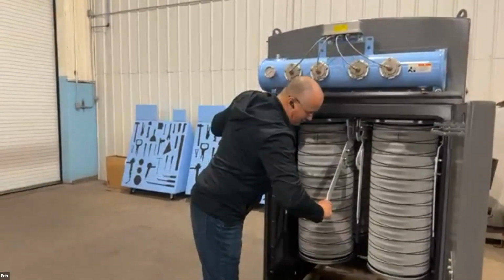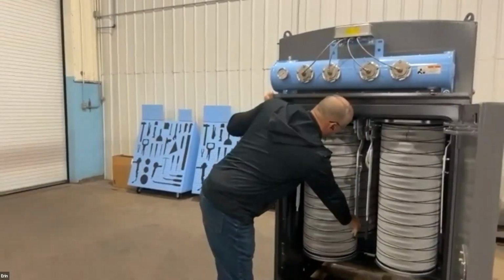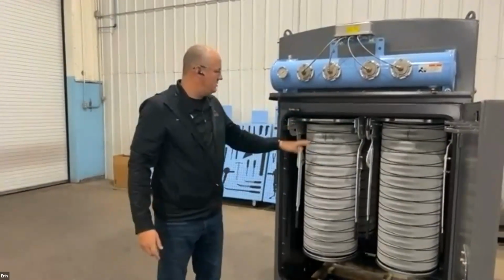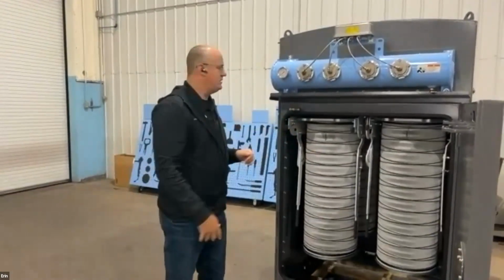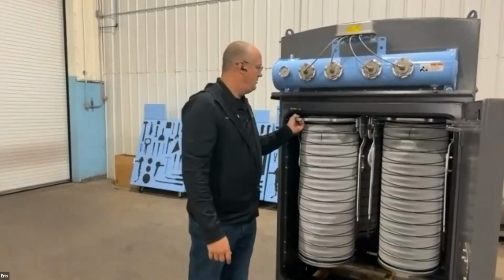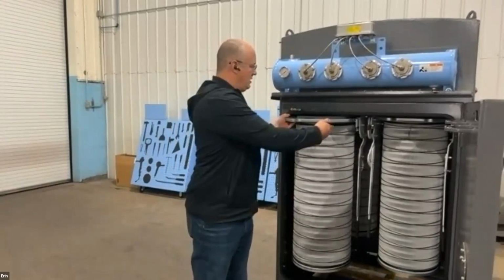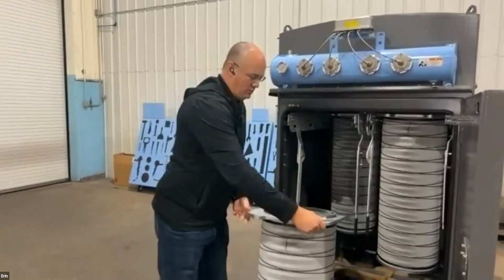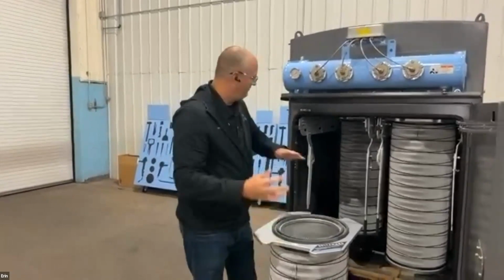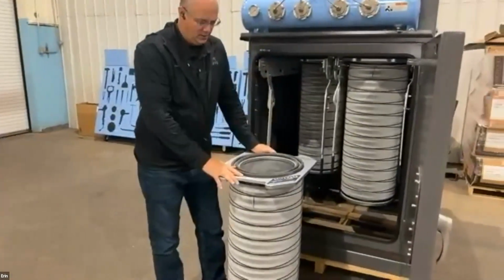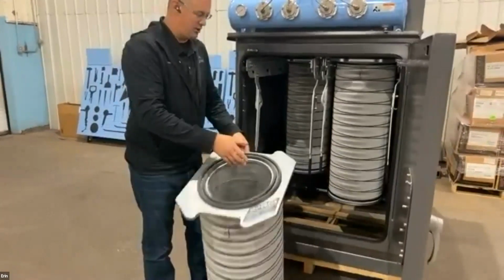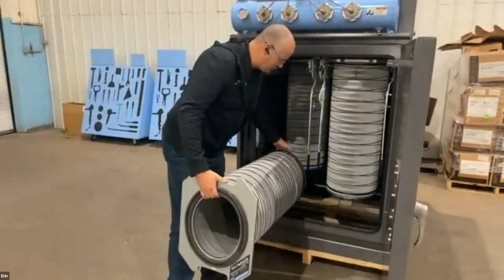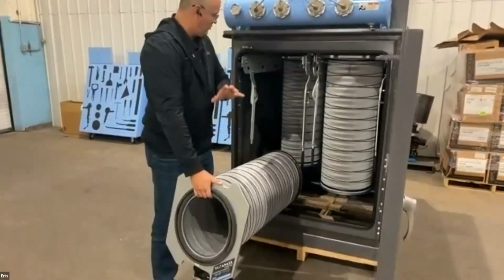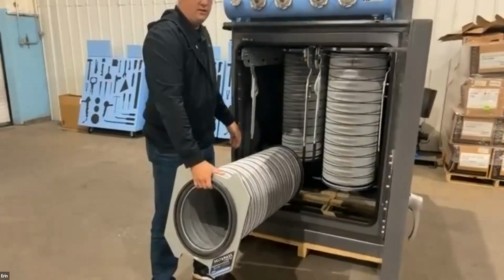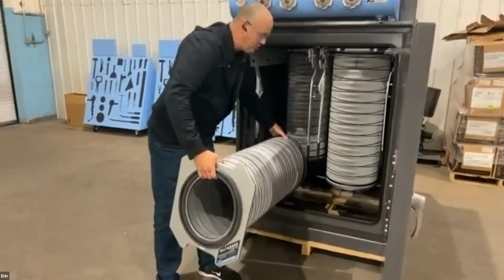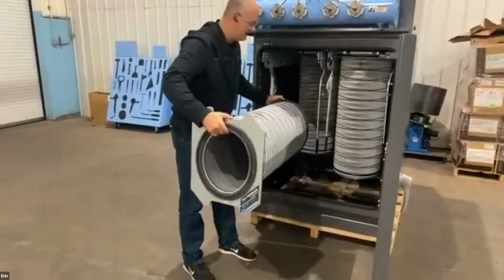A couple of things you're going to notice that are a little bit different about our collector than other collectors is the rail system. The way that these filters go into a C-Max dust collector is slightly different than the way you'll see them in other collectors. So this is what we call a vertical style collector. The filters go in here, get loaded in vertically. There are other collectors on the market that are horizontal style collectors. And that means that the filters will be sitting in this direction. They would go in through a small door, typically on the front, and then the filters are stacked on top of each other like a ladder.